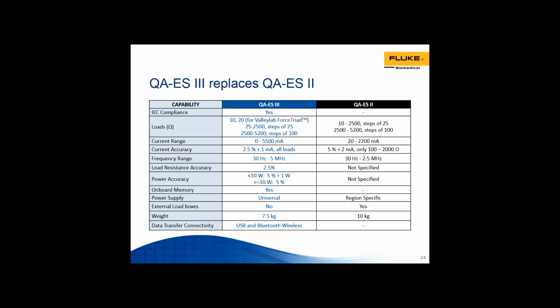We have some end users that might be wondering what the differences are between the QA-ES2, the predecessor to the QA-ES3, so this summarizes that. As you can see, we've added the IEC compliance. There are more loads for testing a different variety of ESUs. The current range is doubled. We're up to 5,500 milliamps with this one. The current accuracy, as I had mentioned before, you can see here that it's twice as accurate. Also, the frequency range for this product is up to 5 megahertz, which greatly enhances its capability to test more electrosurgical devices.